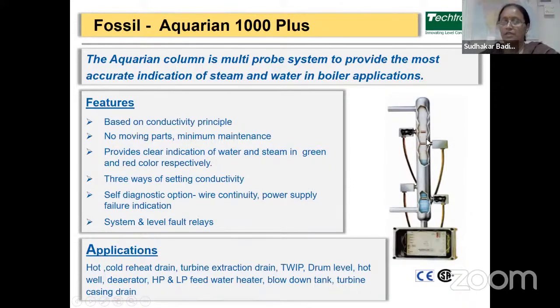And then they can be fitted on the column at the required points or at the required levels. It has no moving parts, hence minimal maintenance. It provides clear indication of water and steam and gives you the indication in green and red color respectively, that is green color for water and red color for steam. The conductivity can be set in three ways. Self-diagnostic options are available, that is for wire continuity and power supply failure indications. Then system and level fault relays are available for safety purposes.